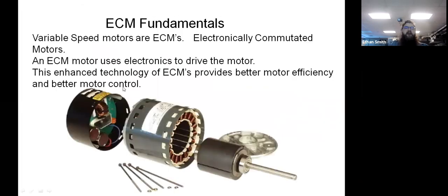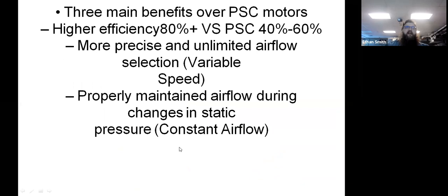Okay, so we're using that electronic package on the back of the motor to drive the motor, manage that 3-phase system so that we can run this thing up, run it down, change the frequency and the voltage that we're delivering to those windings, and get that variable speed functioning. The biggest advantage to the homeowner on this is efficiency. Okay, they're higher efficiency than PSC motors, which typically run about 40 to 60% efficiency. A variable speed motor is going to typically run 80% plus electrical efficiency. We also get the added benefit that we can control the airflow more precisely and maintain that airflow through a wide range of static pressure changes, so restrictions to airflow.